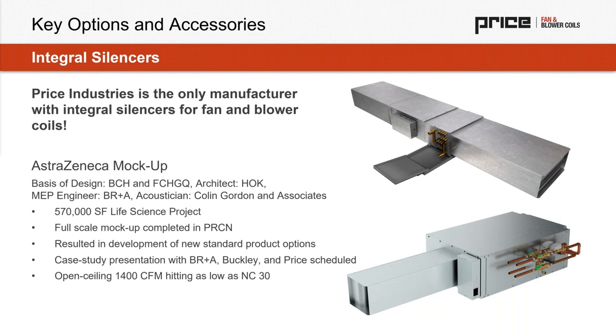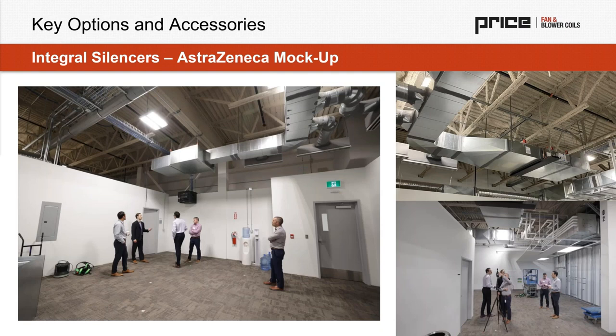So a good example of this would be the AstraZeneca mock-up that we just performed in January. There is a new AstraZeneca project being built in Cambridge. BR plus A is working on that one, HOK being the architect, and then an acoustician from the West Coast. This is a very large project that has open ceilings, and it's a lab office split building. The open ceiling zones required up to 1400 CFM, and in some cases as low as NC30. So harsh acoustical constraints with very high load. And in order to manage this, Price and Buckley and BR plus A in partnership decided the best way to proceed would be to mock up and build this.